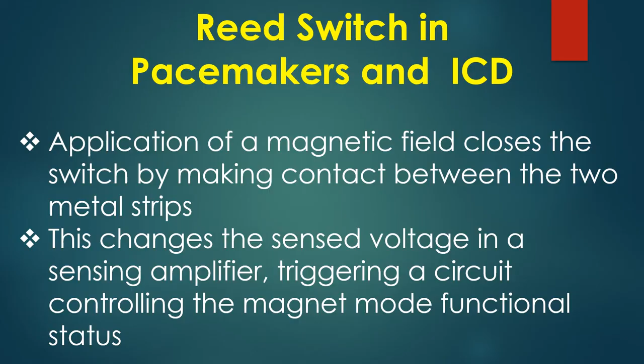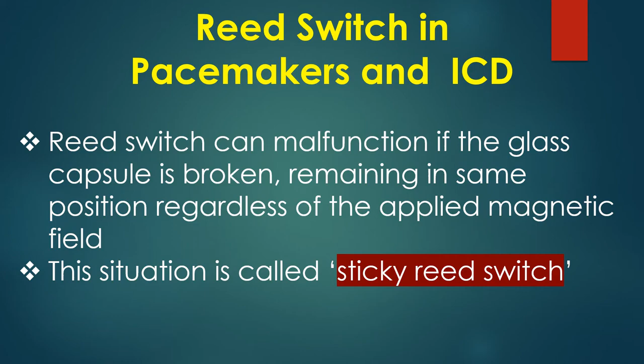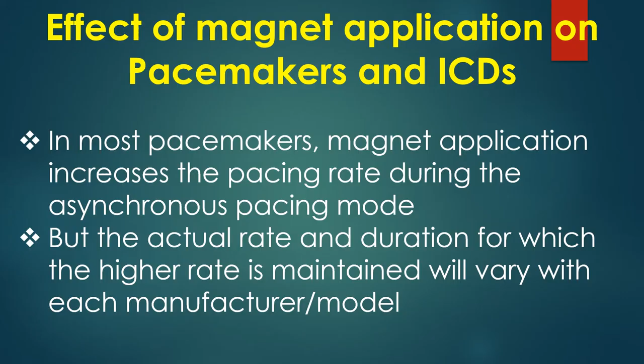Reed switch can malfunction if the glass capsule is broken, remaining in same position regardless of the applied magnetic field. This situation is called sticky reed switch. The exact effect of magnet application on the various functions of pacemakers and ICDs will depend on the make of the device and the programmed parameters. But in general, the effect on pacemaker is that it stops sensing and functions in an asynchronous pacing mode. In case of ICDs, magnet application suspends all anti-tachycardia therapies without affecting the pacing mode. In most pacemakers, magnet application increases the pacing rate during the asynchronous pacing mode, but the actual rate and duration for which the higher rate is maintained will vary with each manufacturer or model.